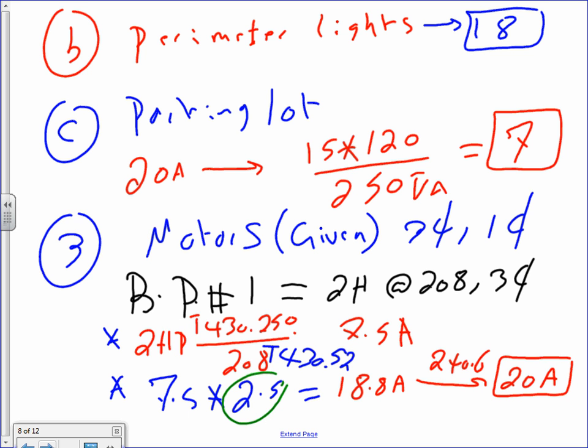Okay? Now remember how to do branch circuits for motors? These are given. So here's a 2 horsepower dedicated circuit. From table 430.250, it gives you 7.5 amps. You remember how we did the calc for the motors? You take 7.5 multiplied by 2.5. Why 2.5? It's a motor. You end up with 18.8, and the next standard size is 20 amp. So that's how you do the branch circuit for motors. This is how we size the overcurrent protection device, 20 amps.